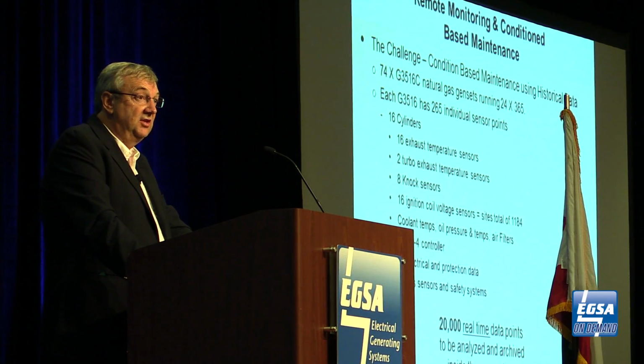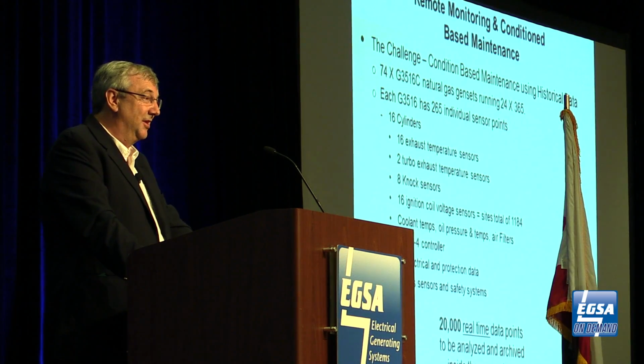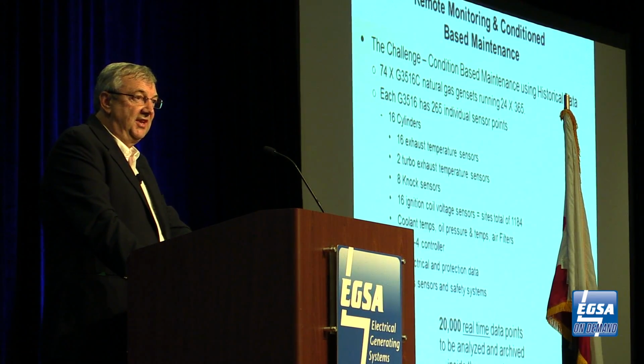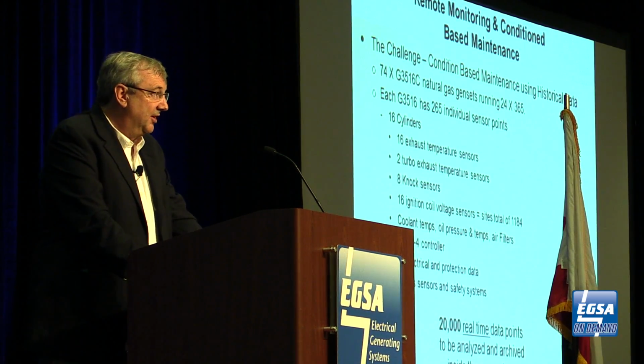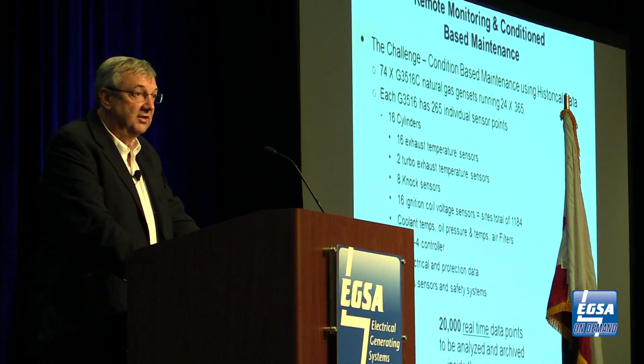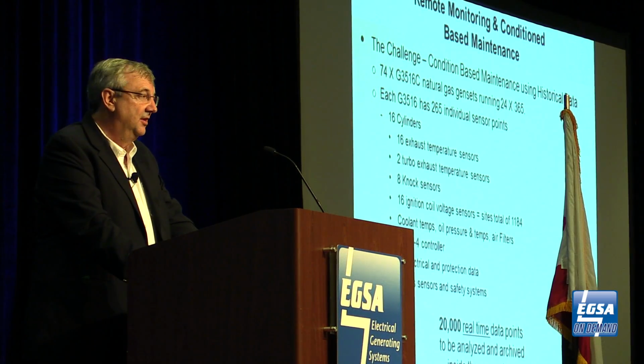Take the engines down when we need to so we can manage our labor force on the site and have what we call unscheduled outages, surprises. We do not like surprises. We want to manage the maintenance and do it in the day shift, and we do that by doing predictive analysis. Do we have enough left on the air filters to get us through to the next shift? What's the risk? Historically, with site conditions, yes, we'll make it another 24 hours. Take the engine down. Is it coinciding with oil service intervals? Is it coinciding with the valve lashing? Doing oil analysis, putting labs on the site.